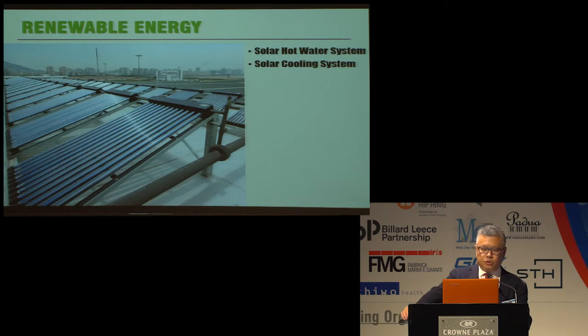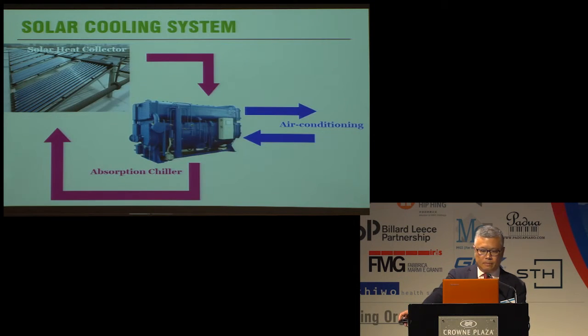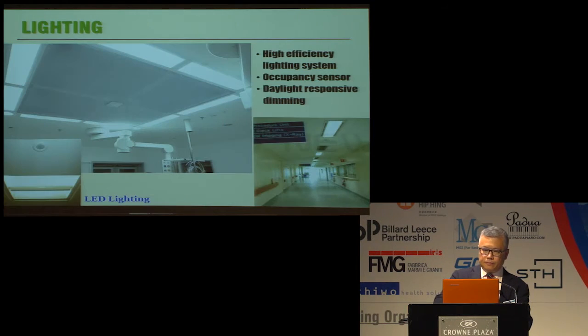A solar hot water system is also a worthy investment of renewable energy technology for hospitals because of the high water demand. And normally, we can actually achieve a payback period of 2 to 3 years. Solar energy can also be used to provide cooling. Solar cooling systems use thermal solar collectors to provide heat energy to drive the absorption chiller that produces chilled water for air conditioning. But despite the COP of the absorption chiller being very low, less than unity, the energy is actually free of charge.